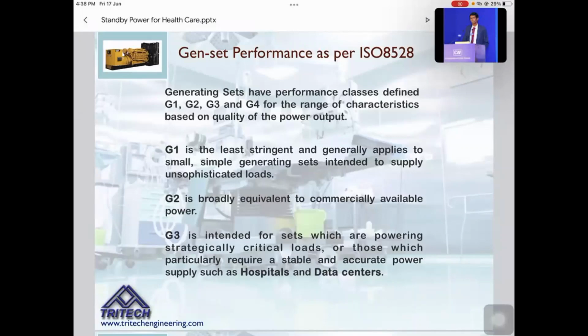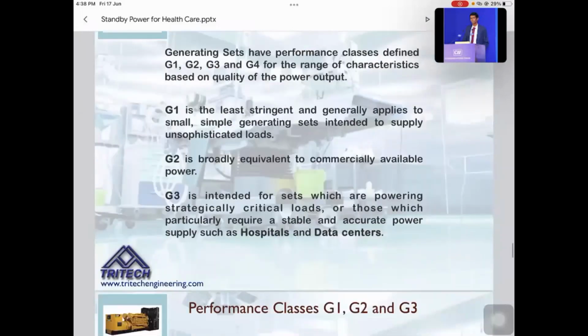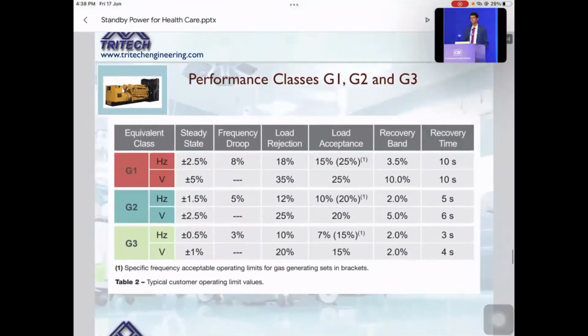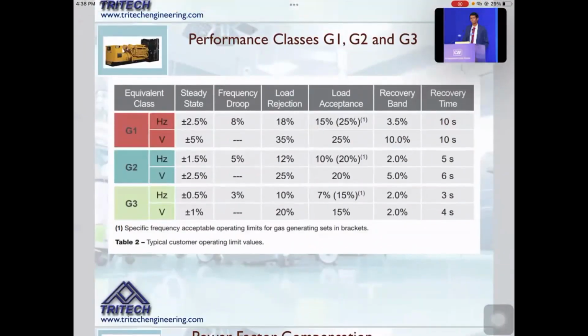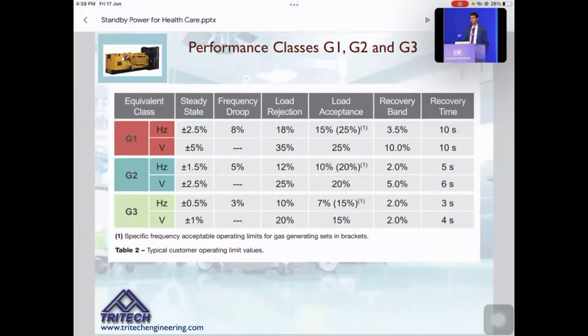I'm explaining the difference between the G1, G2, G3 ratings in the next slide. You can see the G3 rating generators have much faster recovery, and the recovery band is around 2%. Also, if you compare the load rejection and the frequency dip when you are switching off, it is 3% for the G3 and 8% for the G1. These are the international norms on standby generators, the classifications that you need to maintain. So this is definitely a factor to be considered for healthcare projects. I'm talking about the G3 rating.